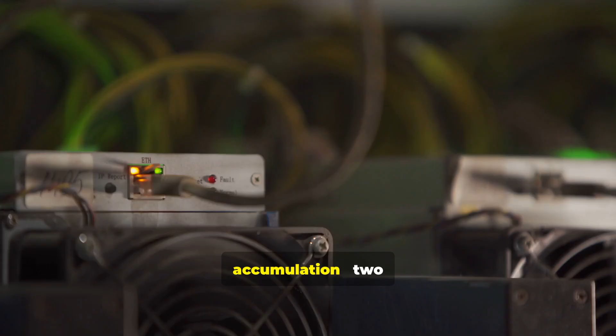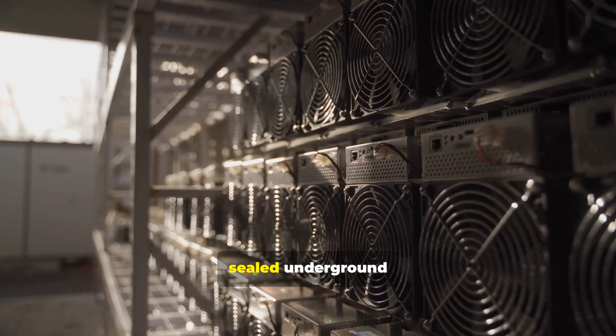The controlled dry environment also helps prevent corrosion and prevents dust accumulation. Two common enemies of electronic hardware. The air in the sealed underground facility is carefully filtered and dehumidified. In a surface building, dust can be drawn in from outside. Pollen can be drawn in as well. Those particles accumulate on heat sinks and impede airflow, which can cause overheating. Humidity can also promote corrosion on connectors and circuit boards. The pristine conditions within the granite cavern mitigate these risks, keeping cooling efficient and connections clean.